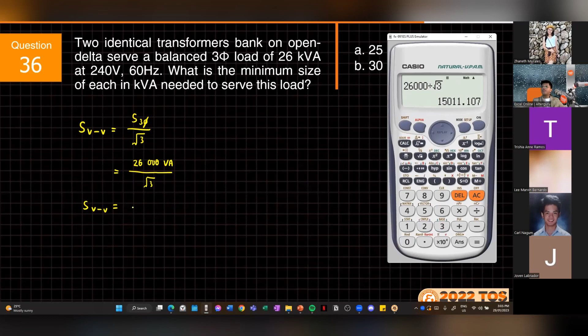So ibig sabihin, it is the minimum size of each kVA to serve the load. Hindi pwedeng kapag naka-open delta siya, tapos 26 kVA, maglalagay ka ng 13-13. Hindi pwedeng ganoon. Kailangan i-divide niyo sa square root of 3, that should be the minimum size, and that's 15 kVA, 15.011, para mapunan niya talaga yung 26 kVA. Okay, so that's for the open delta.